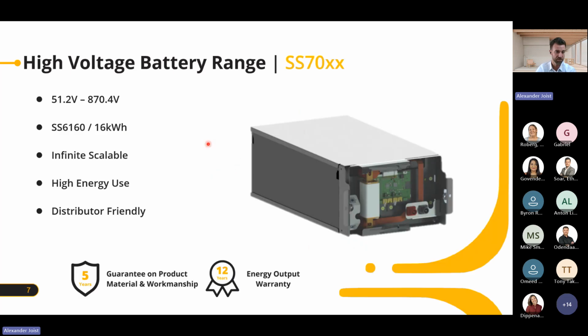The battery module itself has a nominal voltage of 51.2 volt, and combined in total, the voltage range with 17 modules is 870 volt. So we need to always look for that if we are looking at high voltage systems, and obviously also choosing a battery inverter. We need to check the battery voltage.